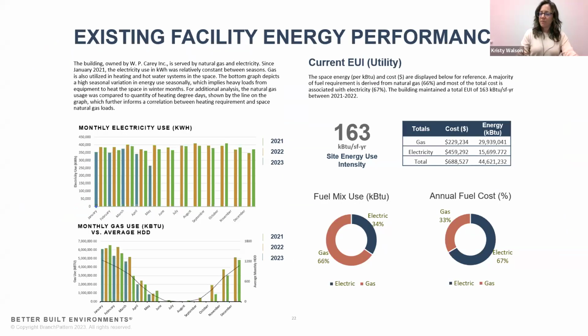First, you assess your existing conditions. In this case, the EUI of the building was 163 kBTU per square foot. You'll notice that in terms of energy used, gas for heating is about 66%, but from a cost perspective, gas is only 33%.